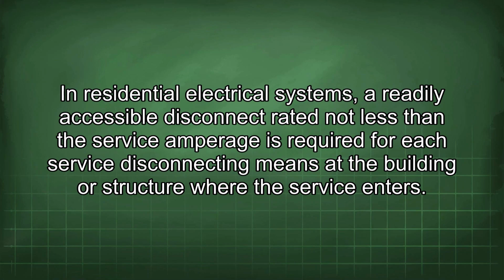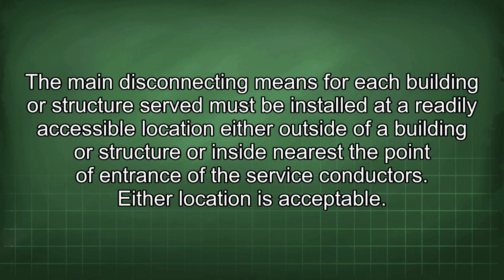In residential electrical systems, a readily accessible disconnect rated not less than the service amperage is required for each service disconnecting means at the building or structure where the service enters. The main disconnecting means for each building or structure served must be installed at a readily accessible location either outside of a building or structure or inside nearest the point of entrance of the service conductors.